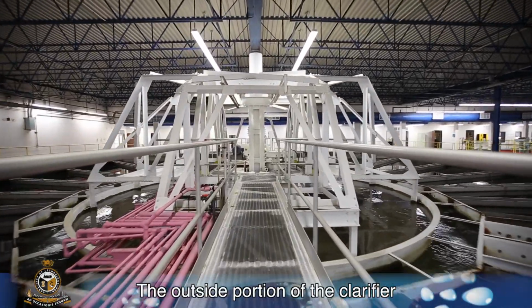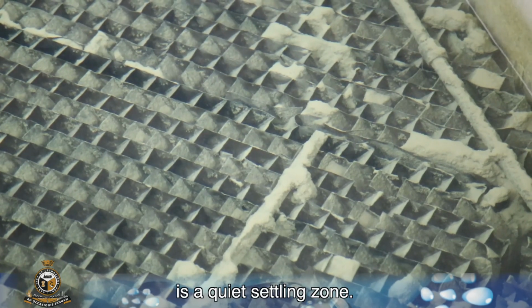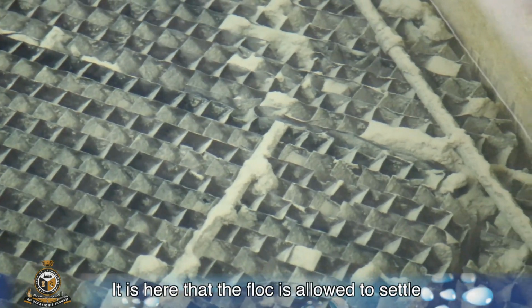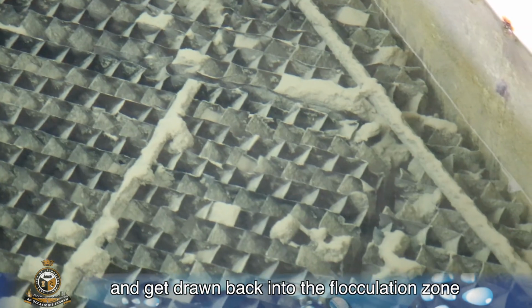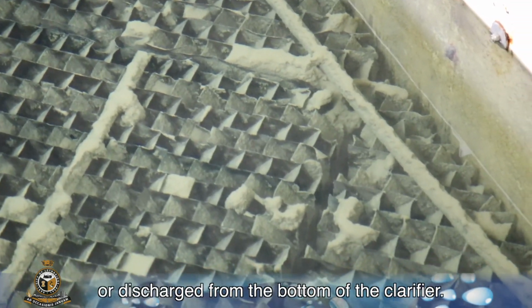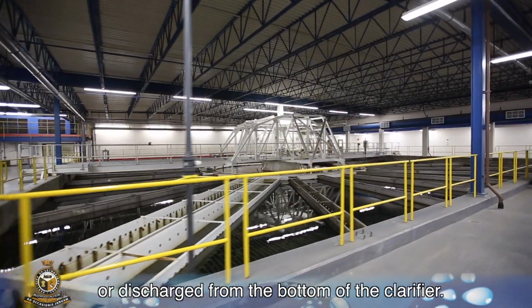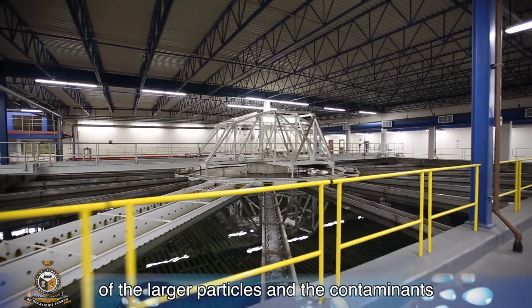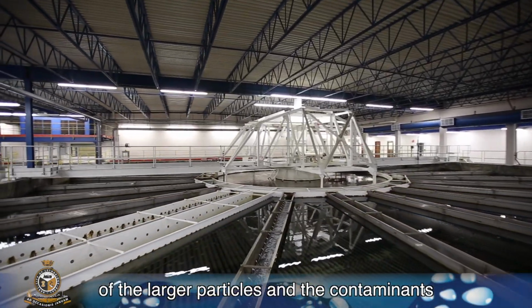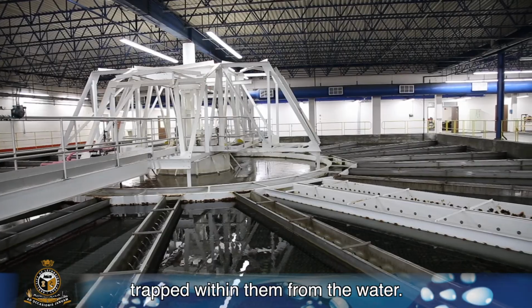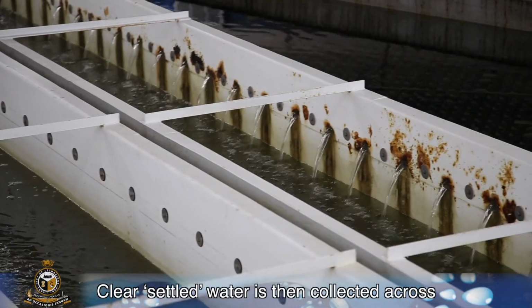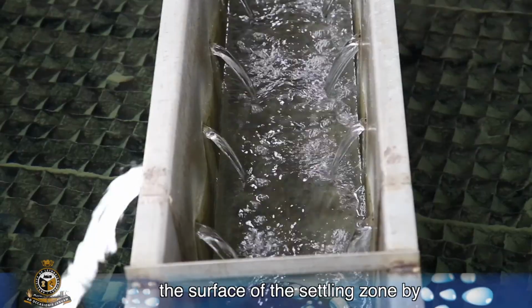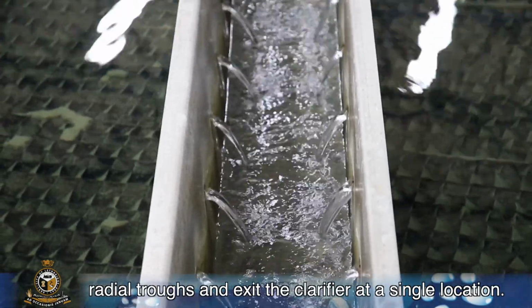The outside portion of the clarifier is a quiet settling zone. It is here that the floc is allowed to settle and get drawn back into the flocculation zone or discharged from the bottom of the clarifier. This settling removes the majority of the larger particles and the contaminants trapped within them from the water. Clear, settled water is then collected across the surface of the settling zone by radial troughs and exit the clarifier at a single location.